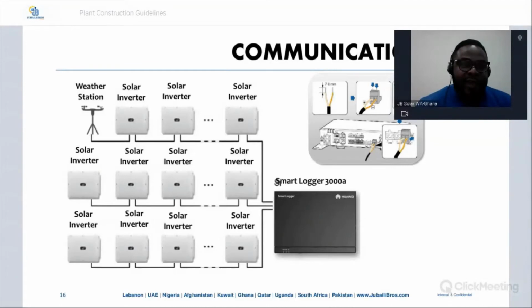If you have any other devices that are not inverters, those devices must always be at the end of the daisy chain, like a weather station, a temperature sensor, or an irradiation monitor. Anything you want to connect to the system has to be at the end of the daisy chain, not in the middle, not at the beginning. It always has to be at the end, like in this picture. So this weather station cannot be in this position. No, it always has to be at the end of this, or at the end of that. Anyhow you like it.